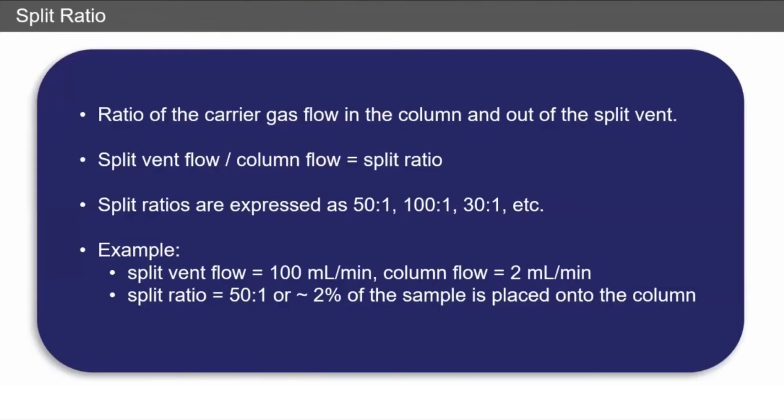Split ratio is typically expressed as 50 to 1, 100 to 1, 30 to 1, etc., and it's just the split vent flow divided by the column flow. So an example here would be a split vent flow of 100 milliliters per minute and a column flow of 2 milliliters per minute. You have a split ratio of 50 to 1, so only 2% of what you're injecting is going onto the column. And this is really important to realize when we're developing sensitivity.